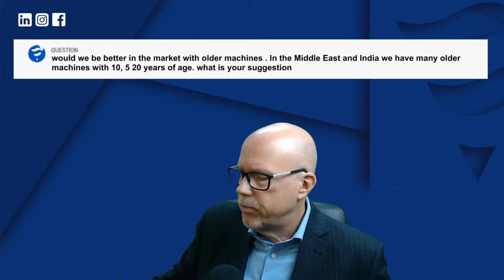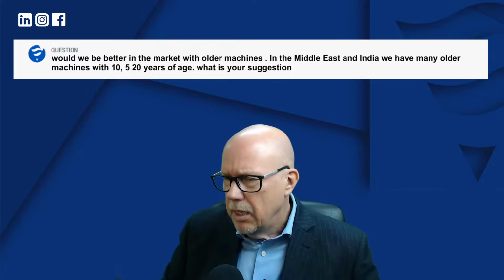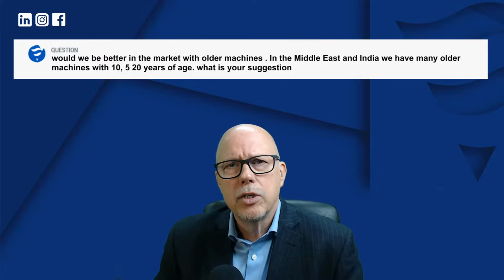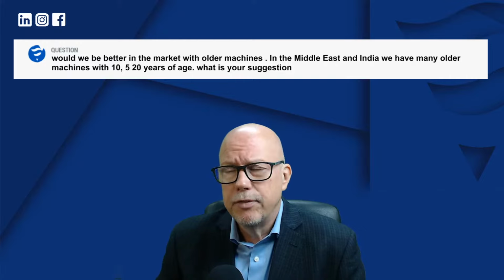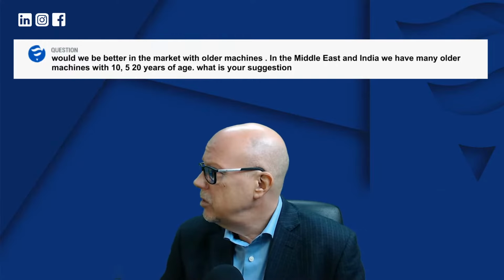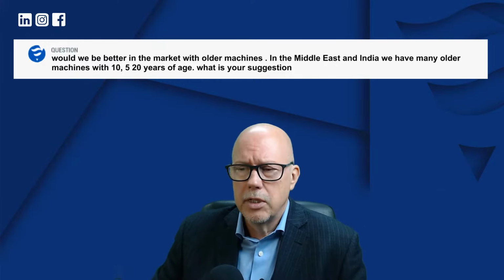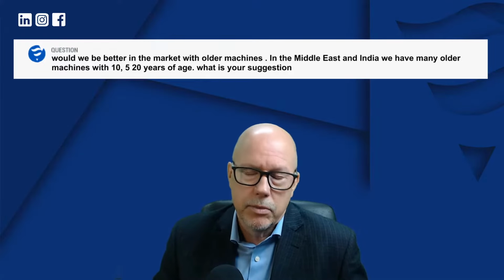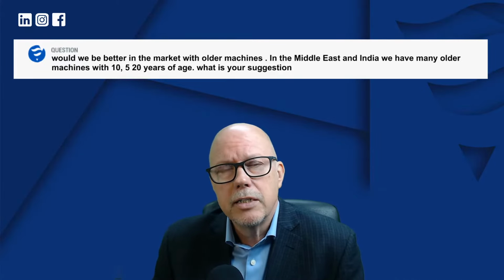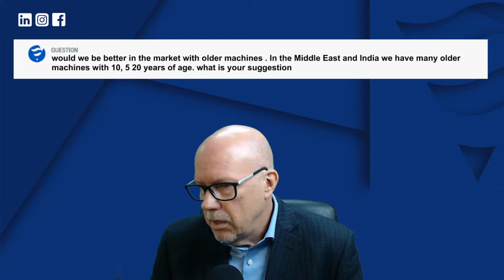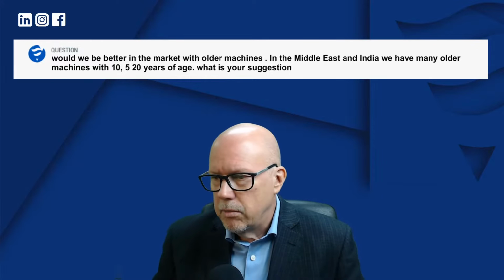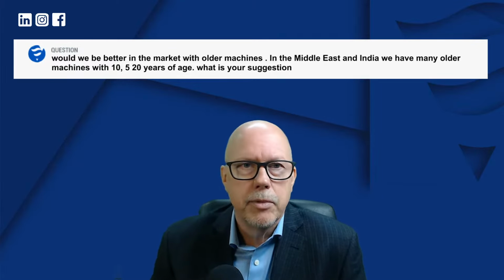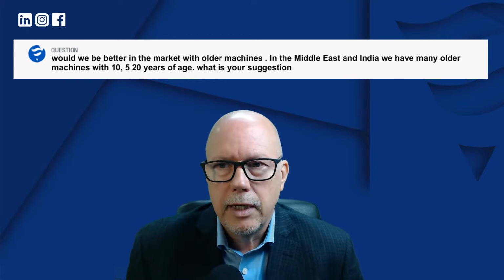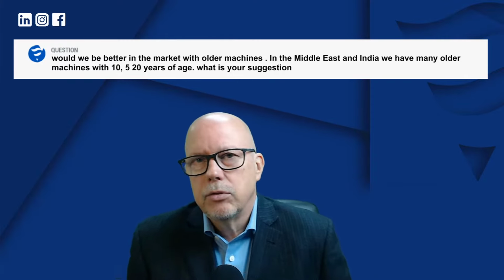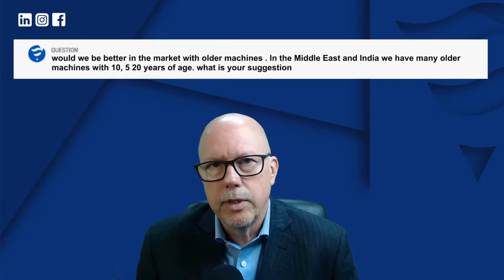Because, I mean, we talk about problems and issues, and most of these, if detected prematurely, are fixable. I mean, the OEM is on site during commissioning, and you spot different issues, and they can fix these. In most cases, they do. Sometimes they can't, but in most cases, they do. So we're not saying all the machines are bad, but what I'm saying is that if you don't have a monitoring system, you don't know. And if I were a utility, I'd like to know during the warranty period instead of knowing 5 years down the line.